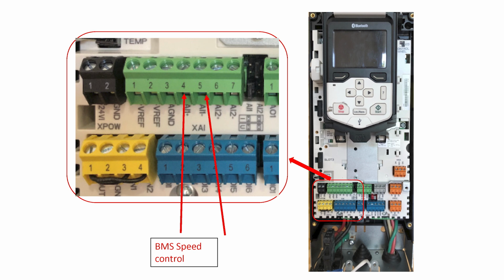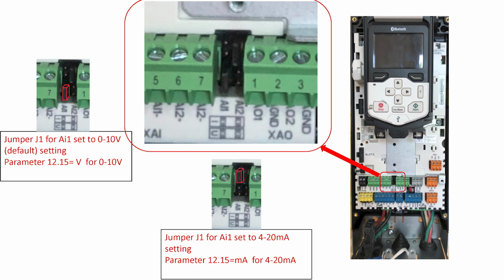Wiring the BMS speed signal. Wire the building management system speed signal to VFD terminals XAI4 and XAI5. XAI4 is positive, XAI5 is negative. If you determine that you need to change from a default of 0 to 10 volts, you will need to change the J1 jumper setting. Refer to the motor wiring diagram in the BAC submittal. To change the setting, you will have to move the J1 jumper and change VFD parameter 12.15.